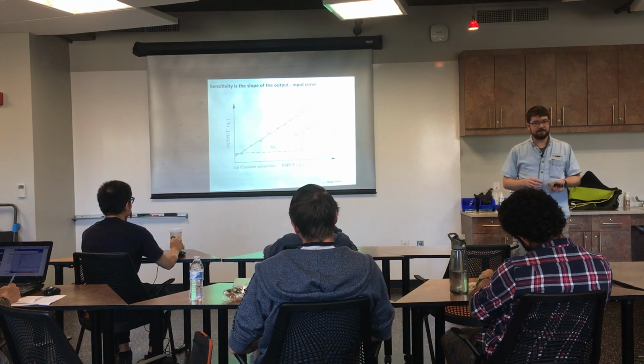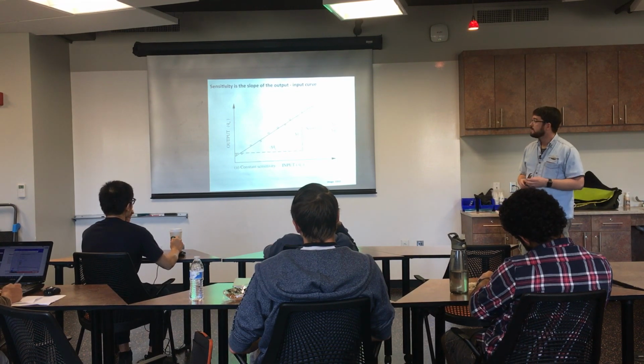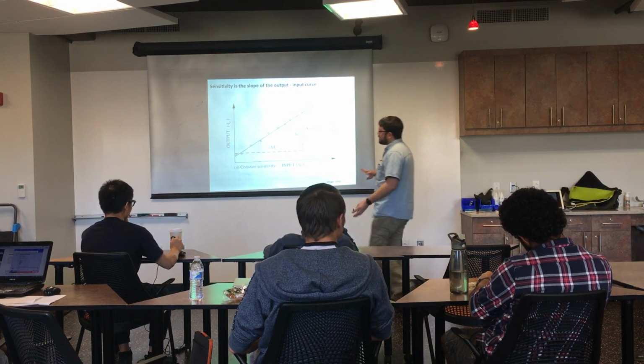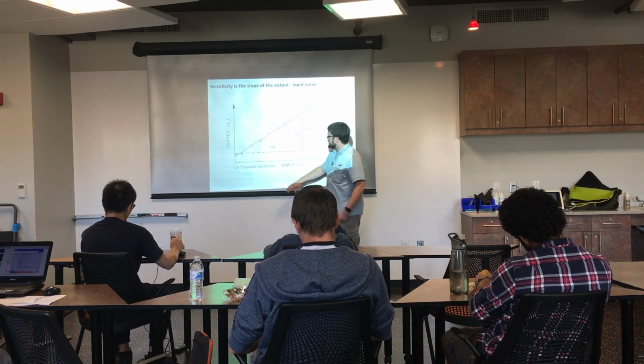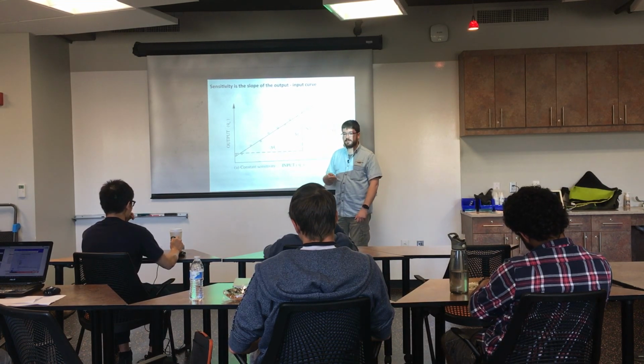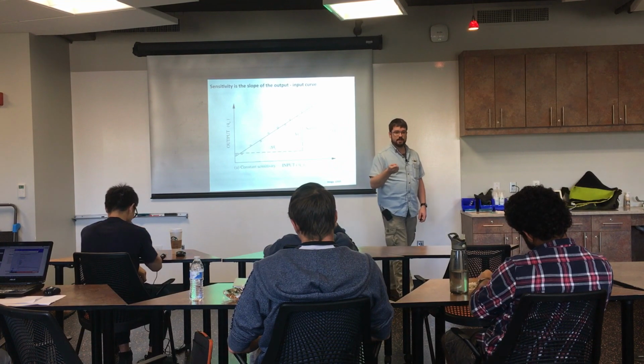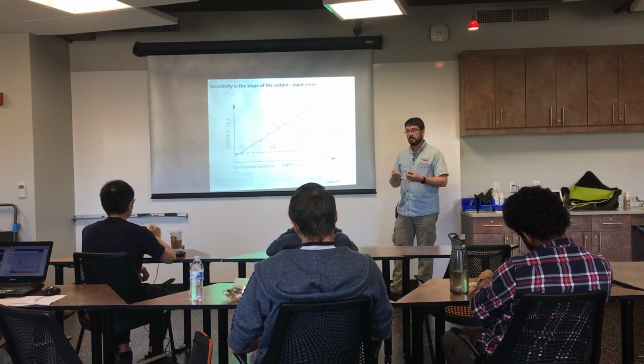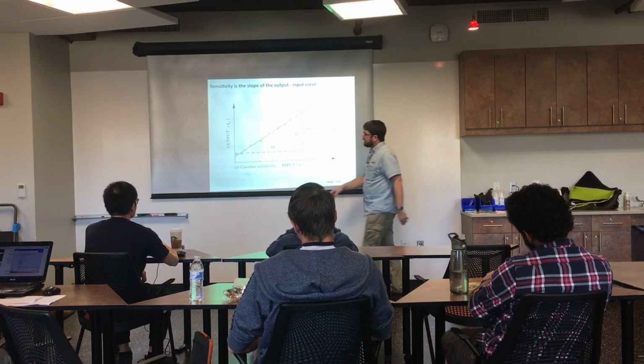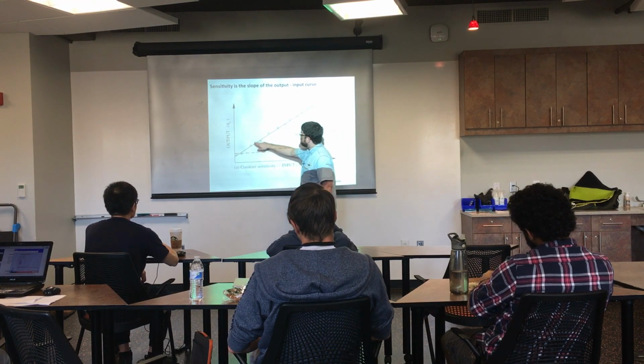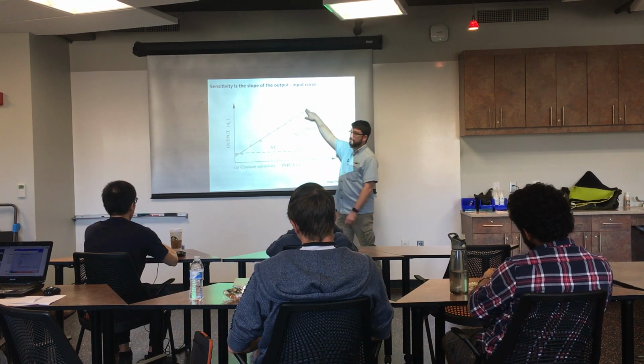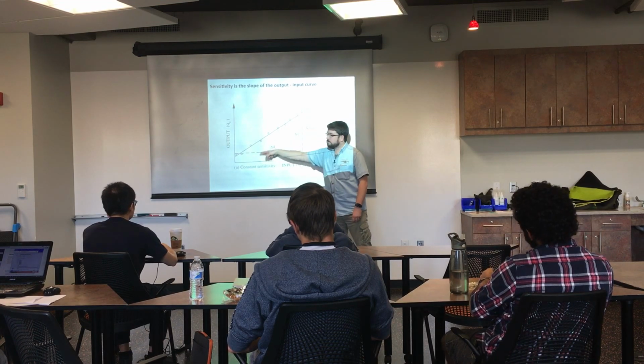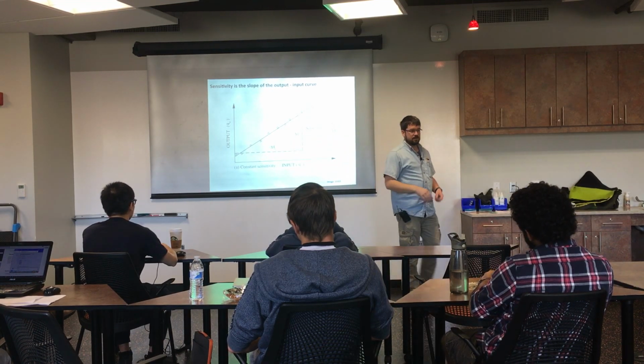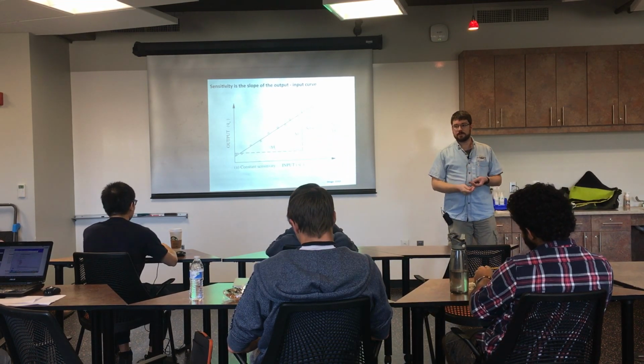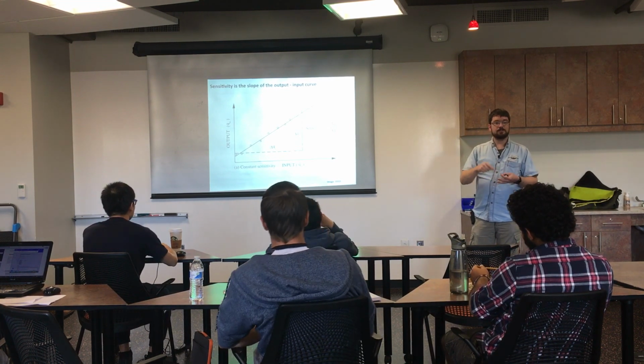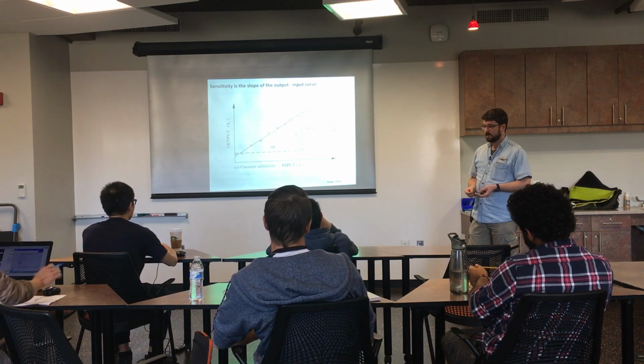The next one is the sensitivity of the transducer. We're going to talk about calibration, like I said, on Thursday, but this is a graph of input. So let's say where we are in space on a displacement transducer, or where we are in force on a load cell, and the output voltage. If we're doing this calibration, we get these data points. And then the slope of the best fit line to those is the sensitivity of the transducer. So how many millimeters per volt or how many kilonewtons per volt does the transducer produce?